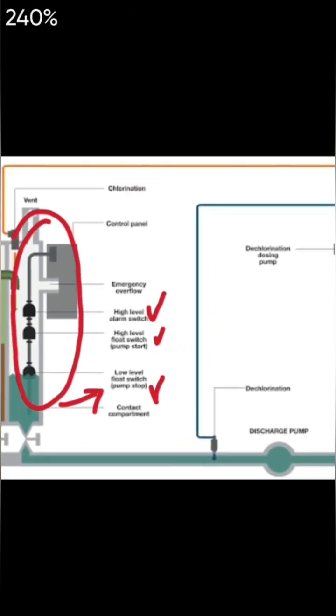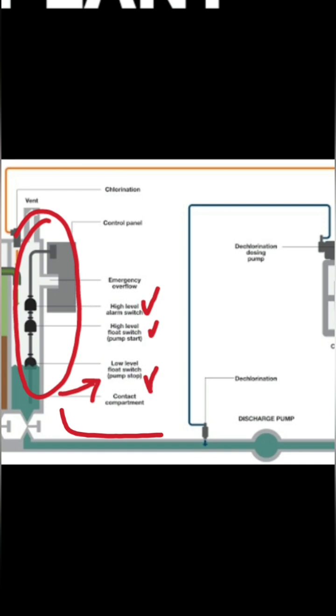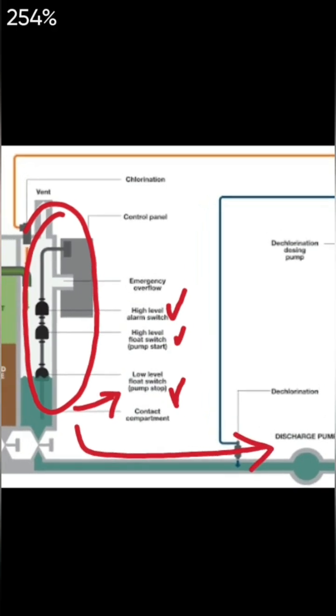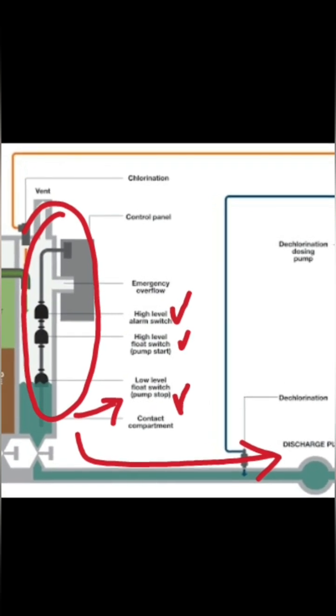The discharge pump is here — you can see the discharge pump. The discharge pump will start when the high level switch, the center one, gets activated. When the low level switch gets activated, the pump will stop.